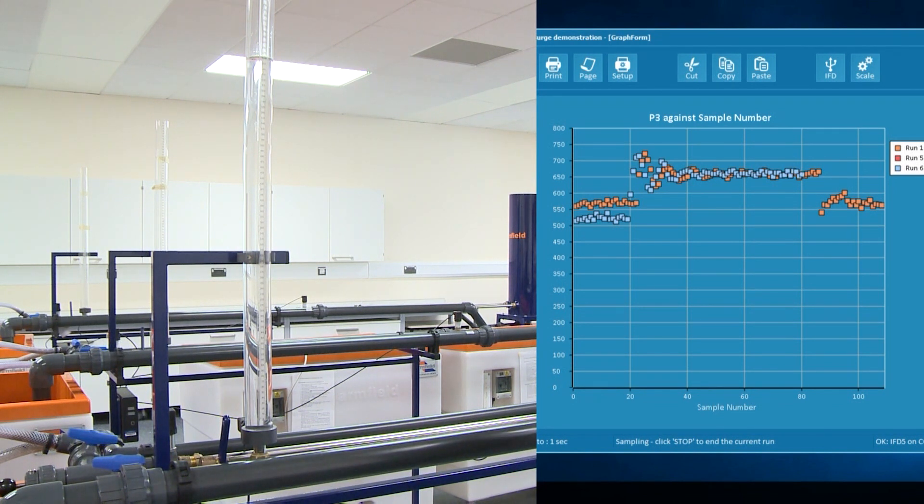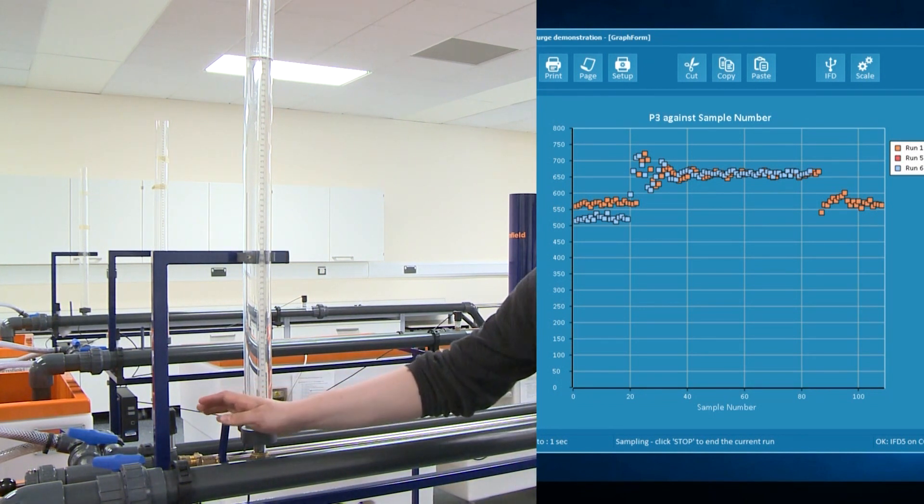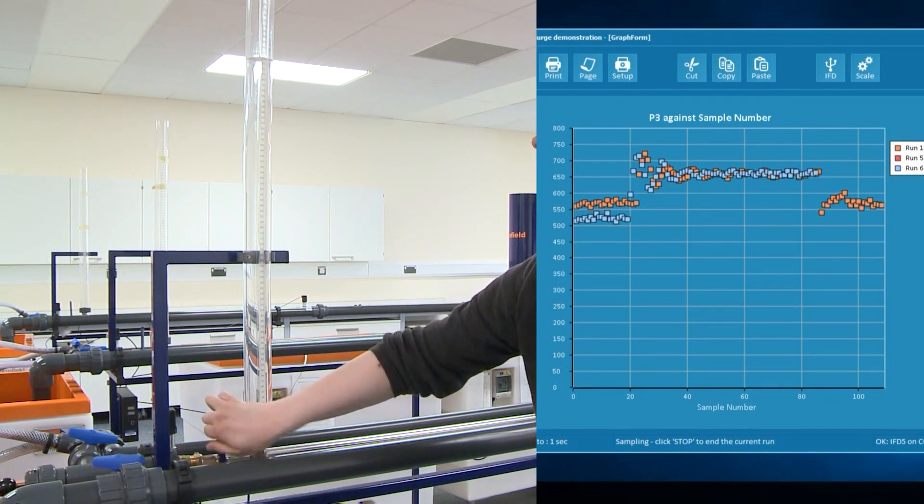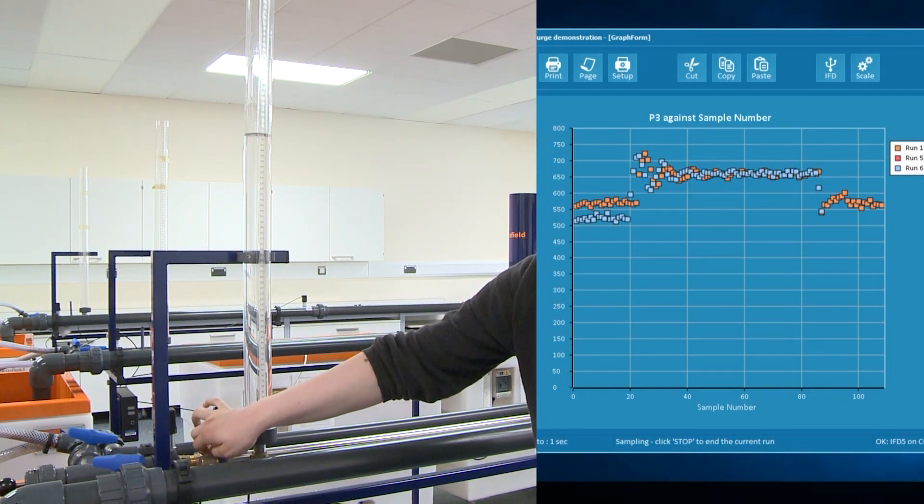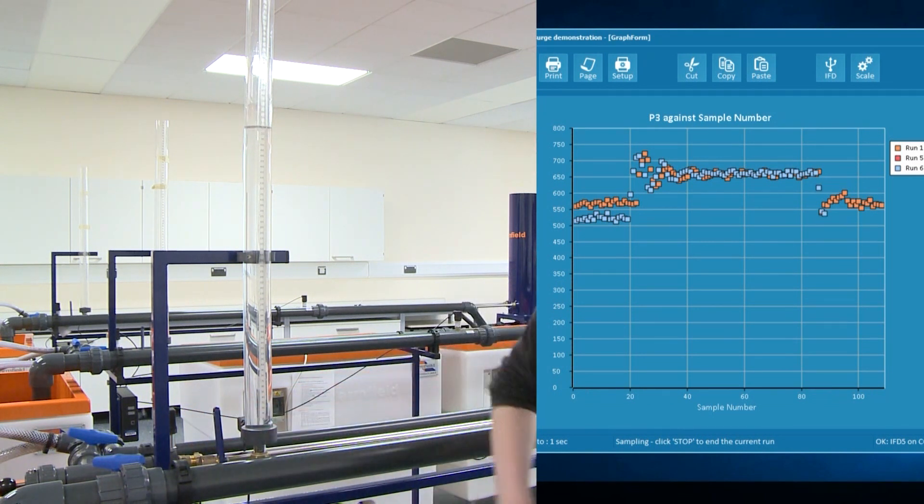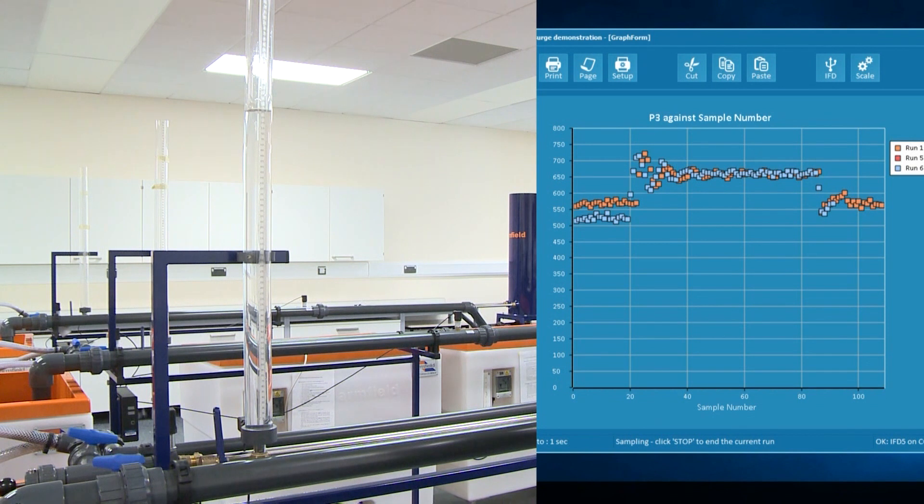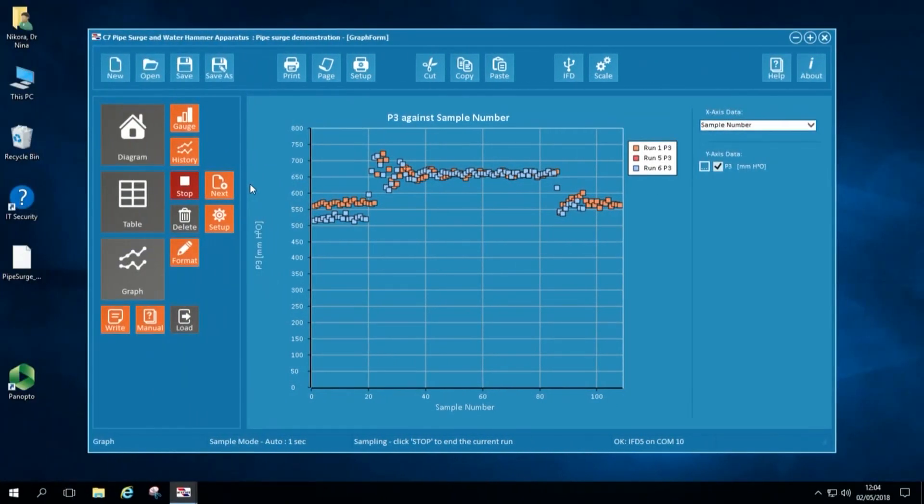When the water level in the surge tower is steady, we open the valve again and we can observe how the water level returns to the initial water level in the surge tower Y0, heavily damped with little or no oscillations.